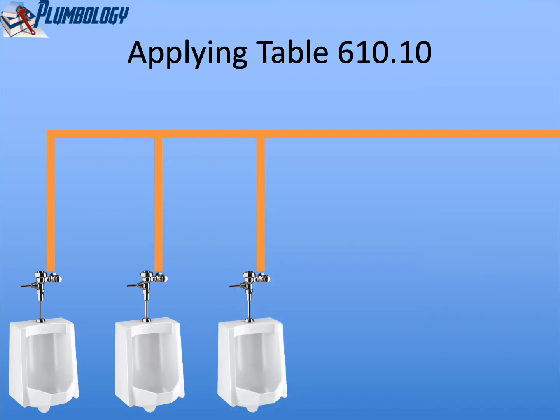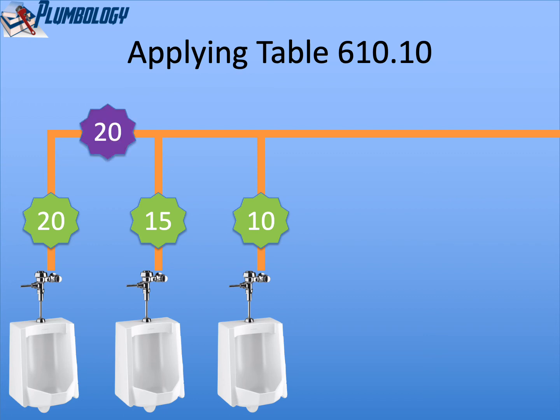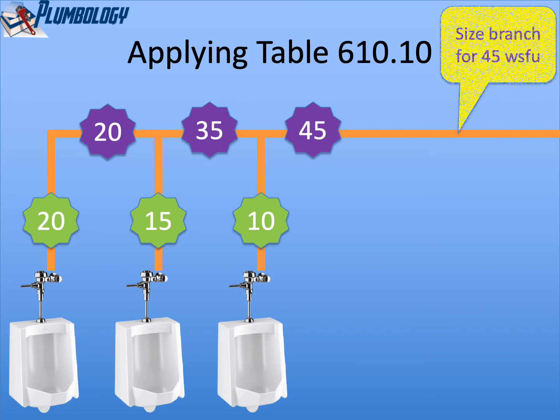If we have three urinal flush valves, same sequence starting with 20, then 15, and the third one is 10. The water pipe segments will be 20 plus 15 equals 35, plus 10 equals 45. We size the branch serving three urinal flush valves for 45 water supply fixture units.